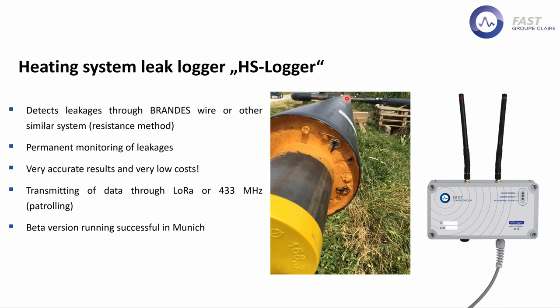Every city who has this infrastructure, usually in Germany, uses the Brandes system. You can see here in this small picture the Brandes wires, which run through the insulation of the pipeline. In the past, we had to use a very expensive, very complicated measurement device from Brandes, the manufacturer of these pipes, to run the measurements for detecting leaks on the heating system pipelines.